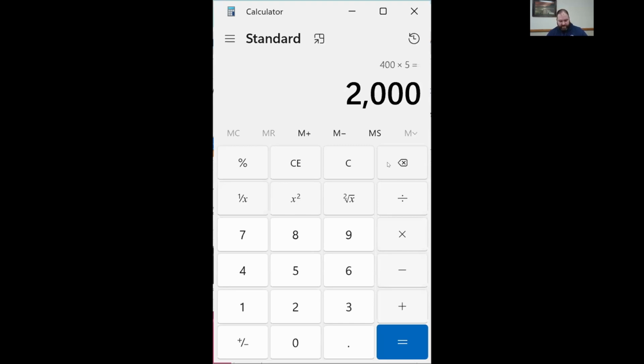And if I punch 2,000 CFM in, let's see, do I even get an 8 by option? I don't. 34 by 10. Yep. I went from a 16-inch round to a 20-inch round. So the ductwork requirements are huge compared to that.